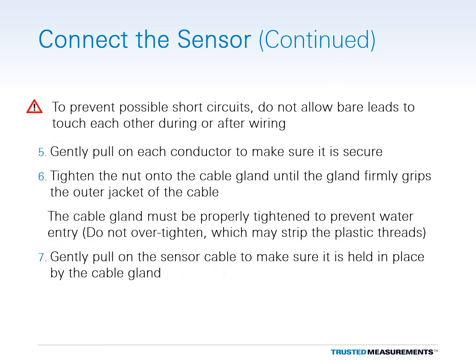Do not allow the bare portion of the leads to touch each other during or after wiring, as this may cause a short circuit. Trim long leads if necessary to ensure there is no chance of a short. After wiring the conductors, gently pull on each one to make sure it is securely connected to the terminal block.